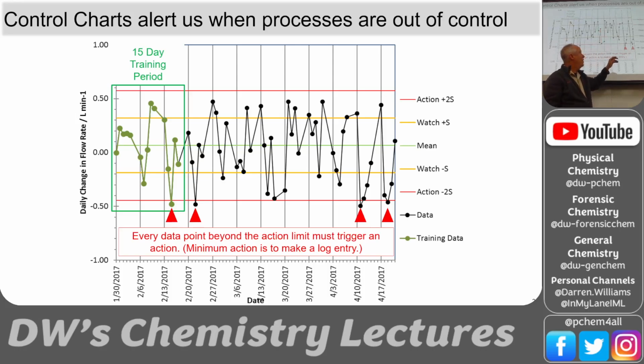The plus or minus 2 sigma captures 95% of the variability if it's random variability. So we should have 1 data point outside that action limit maybe 1 out of every 20 times, so 5%. After 20 measurements, you're probably going to have 1 data point outside that limit if it's perfectly normally distributed. Here we have 4 data points that are outside. So every data point beyond the action limit must trigger an action.